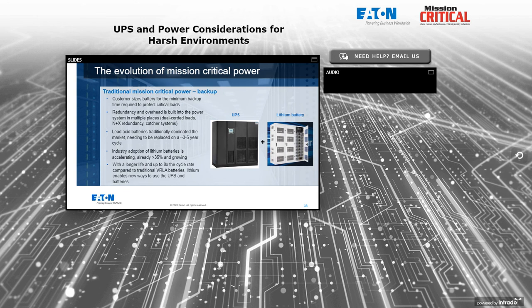But in general, it's a pretty big investment, whether it's an industrial investment or an IT computer system backup investment in both power electronics and batteries. And traditionally, the UPS batteries had to be changed every 5 to 6 years if they're valve-regulated lead acid, which means I need to budget over the lifetime of a 15 to 20-year UPS. I need to budget full battery replacements in years 5, 10, and 15 maybe. That's pretty disruptive to the operations of my critical enterprise, and it's also very expensive to replace all those batteries.